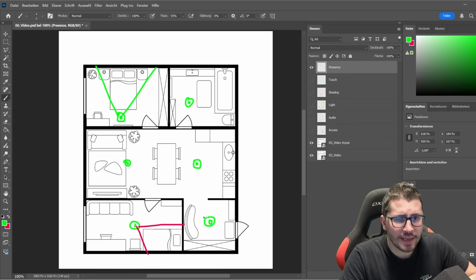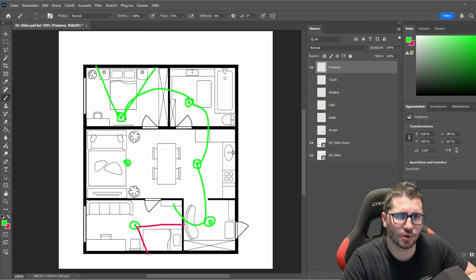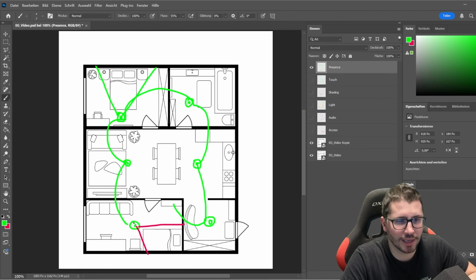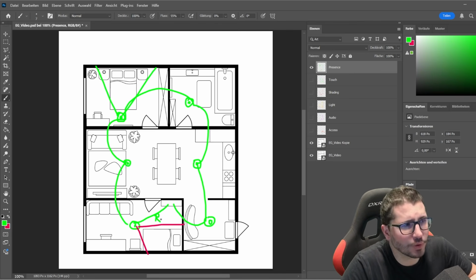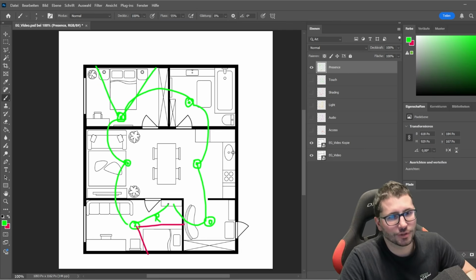Then for the wiring, if you have concrete ceilings and need to pipe it, I would wire it like this: one presence sensor to the next, to the next, to the next. And then from the last one, I also go to the cabinet, but I label the pipe as a reserve, a strategic pipe reserve, because you should not connect it on both ends, or we have the ring again.